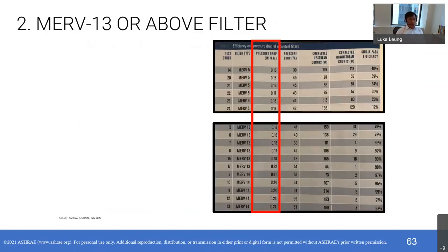But if you just focus on filters, the operating cost of a MERV 13 filter compared to MERV 5 doesn't really increase the static pressure loss, at least if you pick the right filter. So using a MERV 13 filter is not going to increase your running cost significantly. Next slide. So the takeaway so far on first and operating cost is that with good outside air and a good filter, first cost need not be expensive and there may be minimal, if any, increase in operating cost if you use just a MERV 13 filter. But you have to address the risk. Let's look at the risk. Next slide.